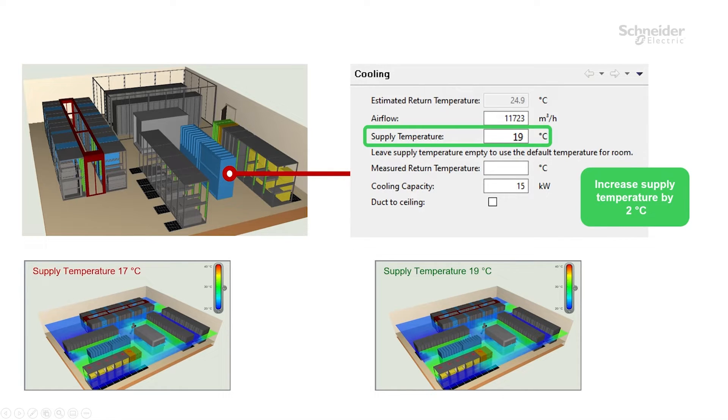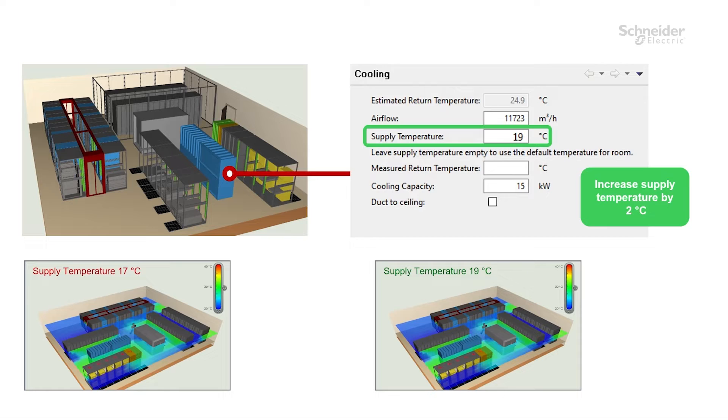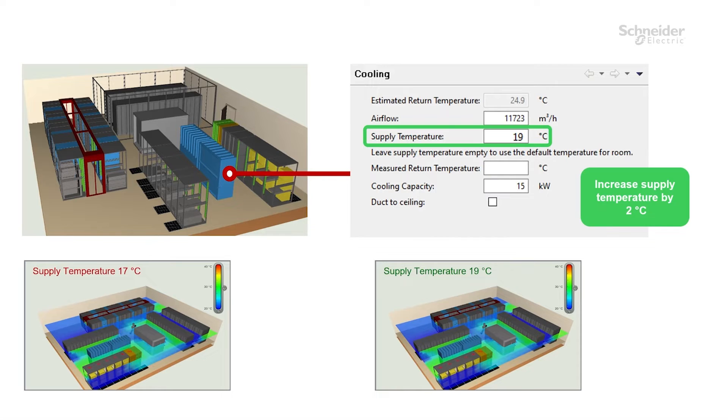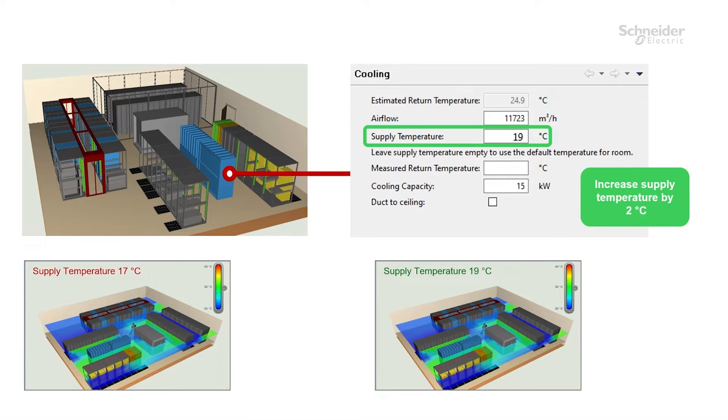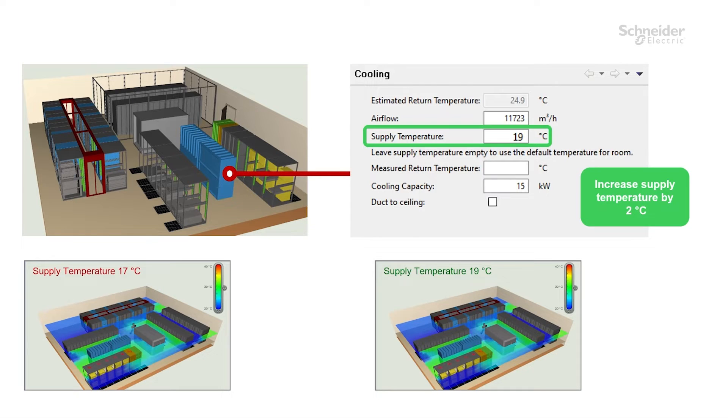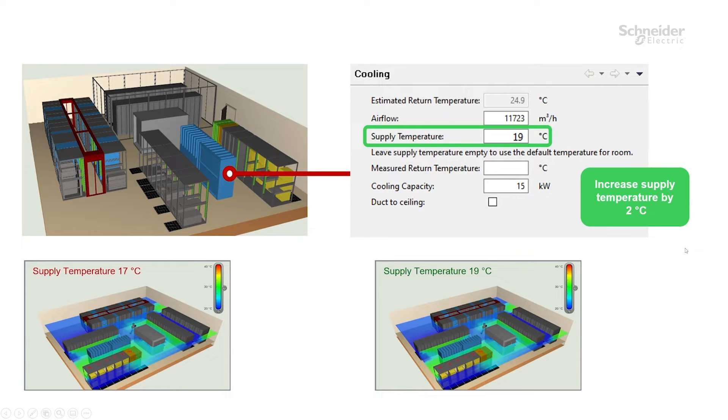After close investigation we see that there is no real difference between these two pictures. This means from the cooling perspective we could use supply temperature 19 degrees, and we will still be able to make sure that the operation of the data center will not be at risk, and the cooling will be as efficient as it is with 17 degrees.